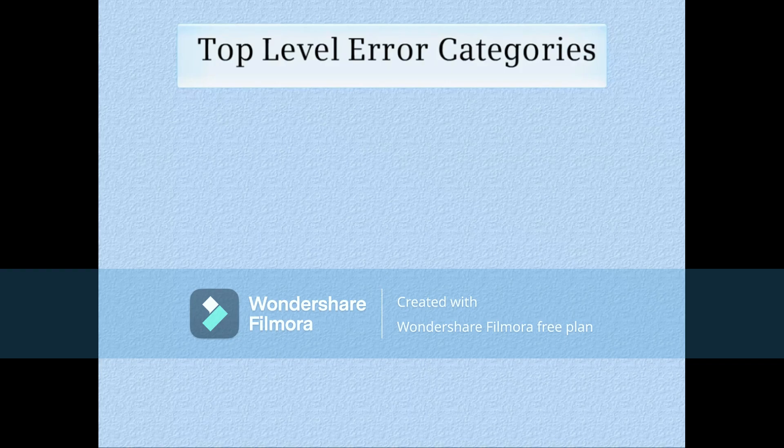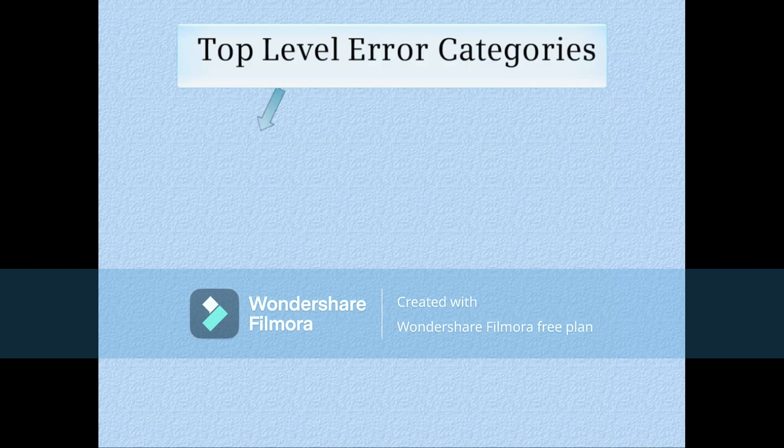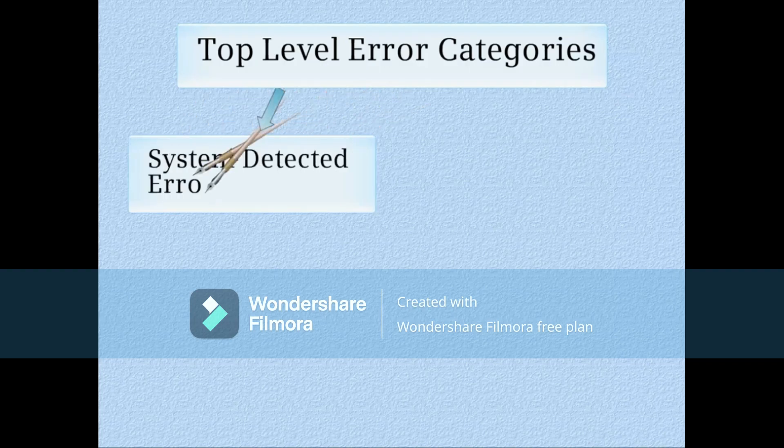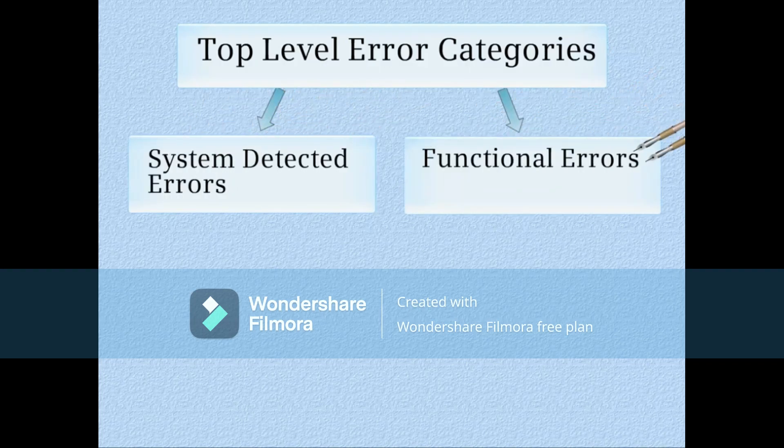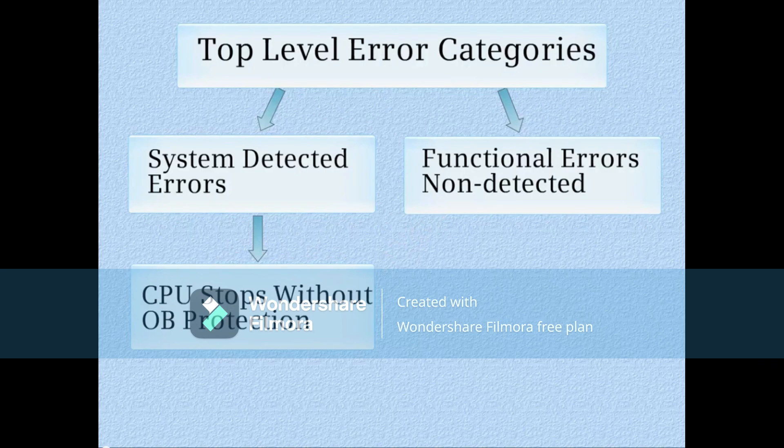At the top level there are basically two categories for errors: those that the system can detect, sometimes called stop errors, and those that the system cannot detect, called functional errors. System detected errors will usually cause the CPU to go to the stop mode if there's no organization block protection. With functional errors something doesn't work right but the system cannot detect what it is and the CPU does not stop.